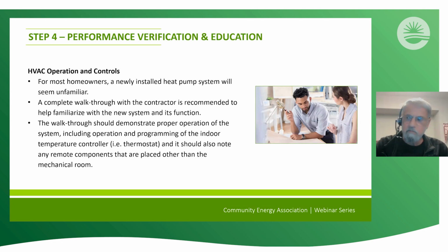There's also things like expectations for maintenance. There's an issue, the heat pump's not keeping up for some reason, and you go there and check it out. You pull the filter out, and it hasn't been changed or cleaned. It's the same one that was put in at the beginning, and now it's loaded with particulates, restricting airflow so much that it's affecting the performance of the system. It's creating noise, or it's not delivering the heat. The refrigerant's not changing states adequately. There's all kinds of issues that can come with that, not to mention it's not good for your lungs, that indoor air quality piece.